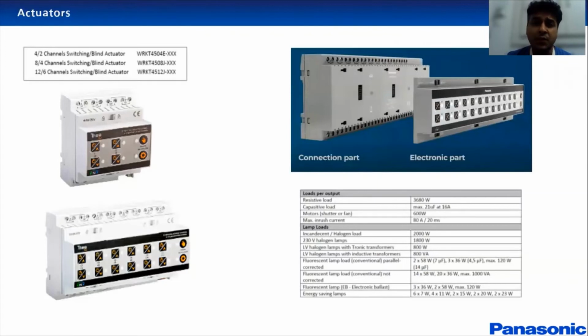These are the actuators we have. We have them in 4-channel, 8-channel, and 12-channel. Irrespective of whether it's 4, 8, or 12 channel, each individual channel is 16 amp, and it can take a high inrush current of 80 amps for 20 milliseconds. You have an option to control both switching as well as blinds in the actuators. You can program and configure this in the ETS.